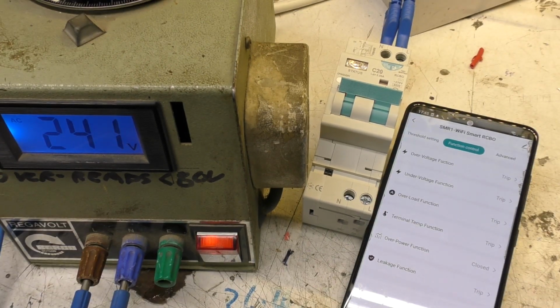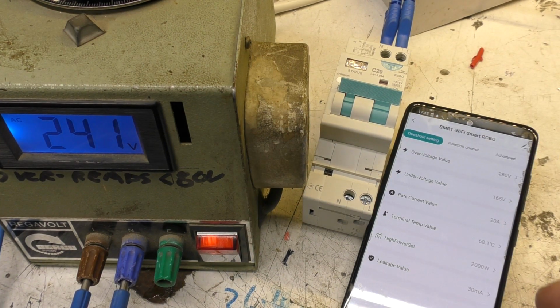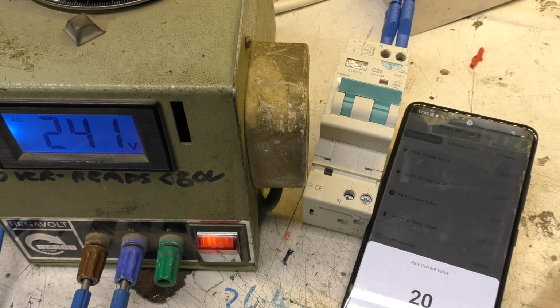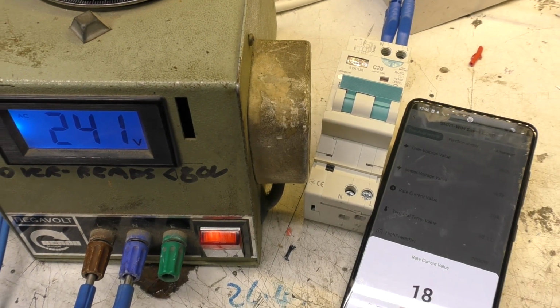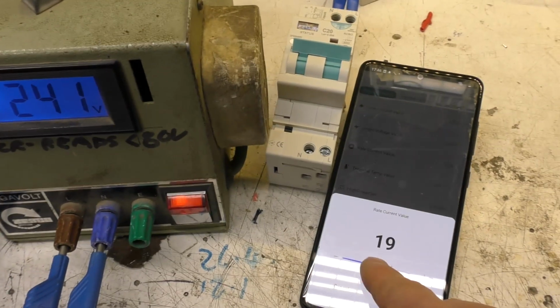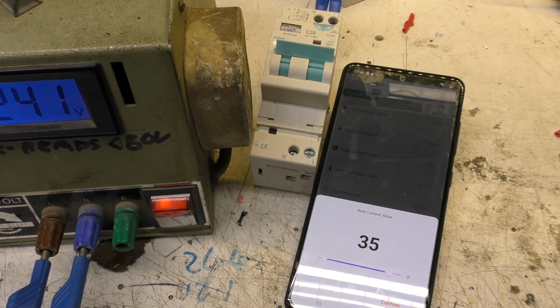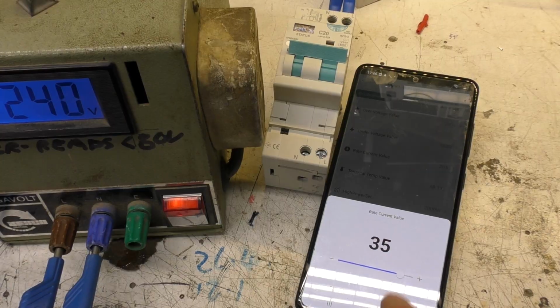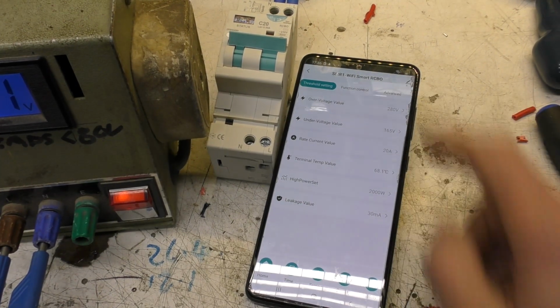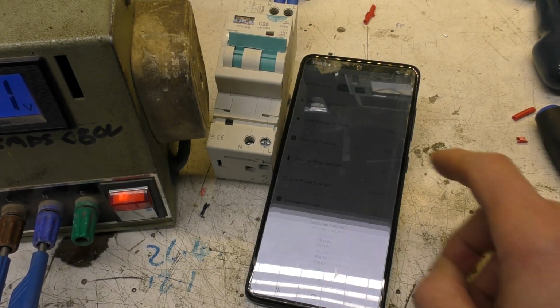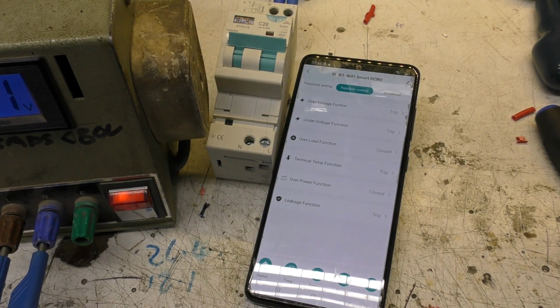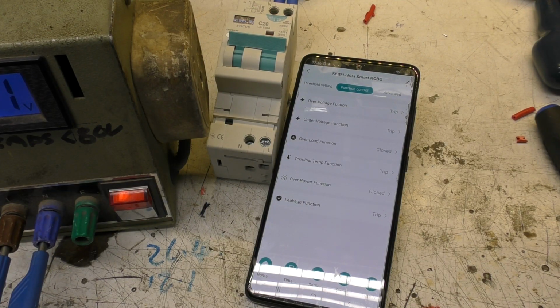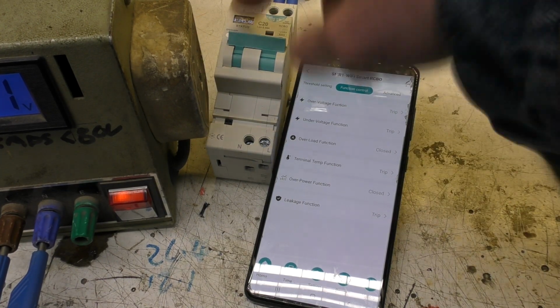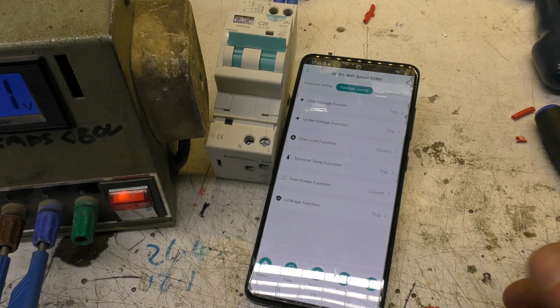So what other stupid and dangerous things can this do? Well, okay, the overload function. This is a normally 20 amp device. It's labelled 20 amps here. Now, it does let you set the current trip, but it won't actually let you set it over 20. You can try, but after a couple of seconds it resets itself, and you see it's set itself back down to 20 for safety. But what you can do, go into function control, and just go to overload, and disable it. Now it doesn't give you any overload protection at all, and there's no indication on the display or anything that this is now not a circuit breaker anymore.